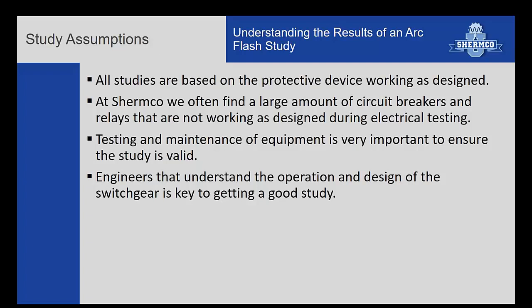Right, and one of the big hazards with arc flash is the pressure wave that it produces. That's why NFPA 70E limits it to 40 calories. Mm-hmm. You can build suits that can protect the body from higher flash, but you also have this big percussion wave coming at you. So I would definitely be worried if that percussion could affect processes. That would definitely be a big concern. Right. You wouldn't want that.